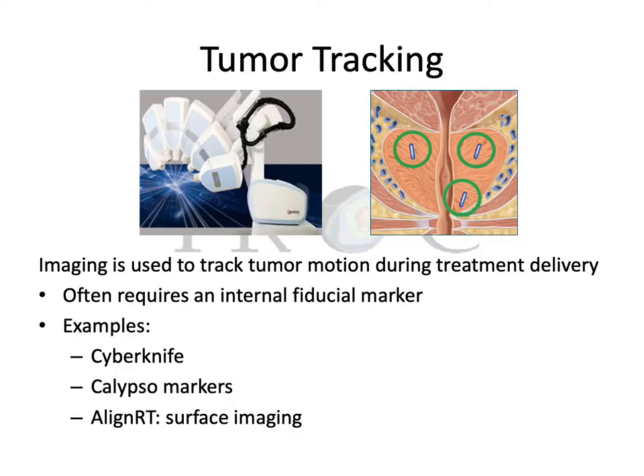Another option for managing intrafraction motion is tumor tracking, which uses imaging to track tumor motion during treatment delivery. This often requires placement of an internal fiducial marker. Examples include CyberKnife — a robotic arm tracking a marker within a tumor and treating the entire time the tumor is moving — as well as Calypso markers placed inside the prostate to tell the machine where the prostate is at all points during treatment delivery. AlignRT is another system that uses surface imaging to do the same thing.